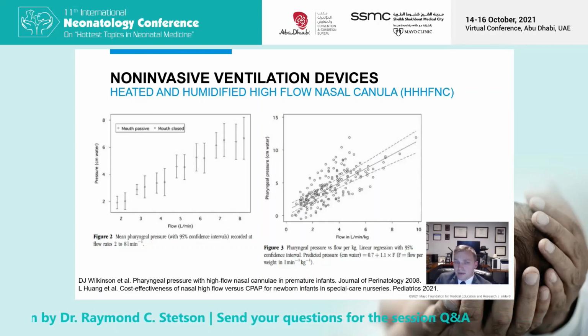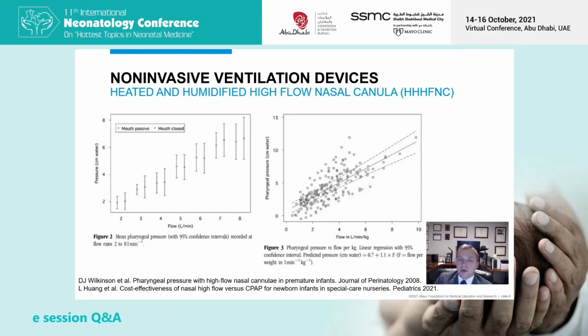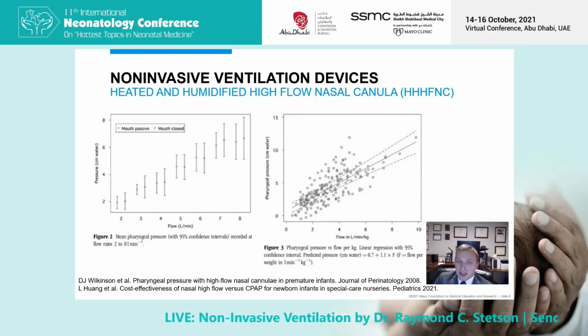High-flow nasal cannula systems have fluctuating airway pressure, and all systems require a pressure pop-off valve for patient safety. When the cannula are occluded, very high airway pressures can be recorded if a pressure pop-off valve is not in place. Wilkinson et al. described an equation to estimate pharyngeal pressures based on high-flow nasal cannula flow rates and patient weights. They also described similar airway pressure measurements for patients treated with high-flow nasal cannula when their mouths were open versus when they were closed.